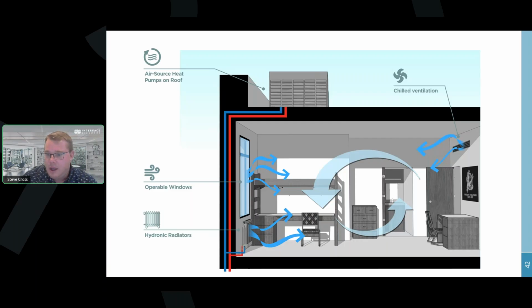I want to be clear here: this strategy was not to add extra radiators to deal with a specific cooling load and maintain a specific temperature. We wanted to know, what if we just used the heating radiators sized only for heating and put cold water through them? How much impact and benefit would that provide?